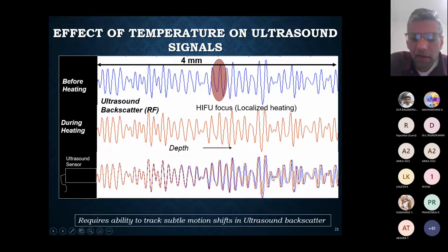As you increase the heating, as you increase the temperature, you will start to see that the red progressively moves away from the blue. And as I said on the previous slide, because of the heating, the tissue scatterers appear to move closer to the transducer. And as I've told you before, wherever the amplitude is high, wherever you see the echoes, that's the location of those scatterers, right?